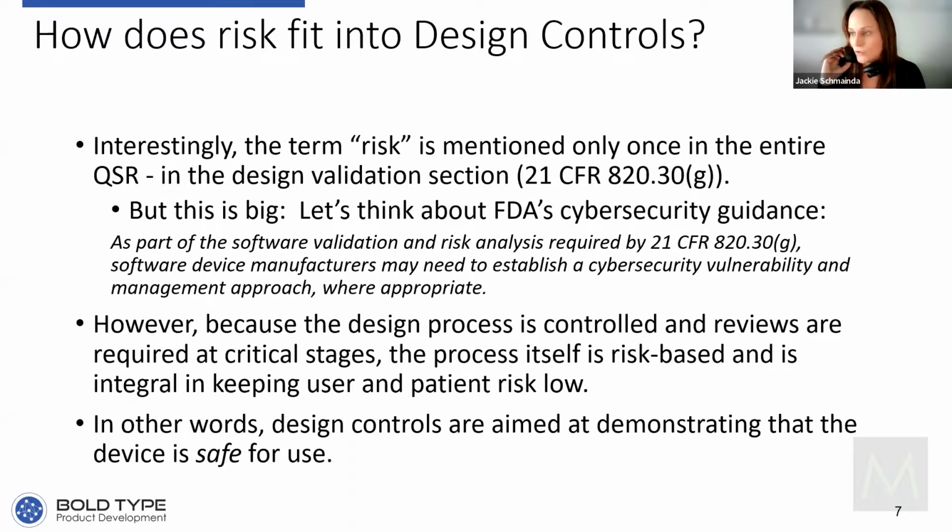All of this leads to making sure that you have a design process that yields a safe device. So again, the key here is the design control process is intended to yield a very safe device. Of course, presuming that you've followed it and you've incorporated reasonable design controls along the way to mitigate significant risks that are unacceptable to users or for the safe use of the device.